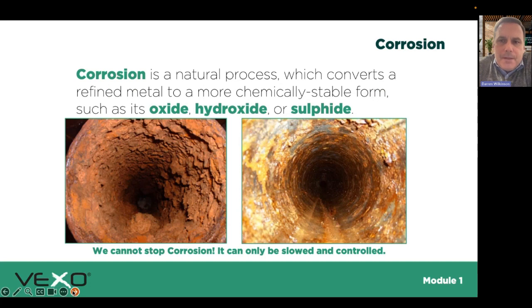So that's scale. Then we have corrosion - a very broad term with various types. But a key point is that we can't stop corrosion. If someone says they can stop it, they can't - it can only be slowed and controlled. The more we keep the system clean, chemically stable, and free from bacteria, the more likely we are to hit the 25-year-plus lifespan we should expect from the system.